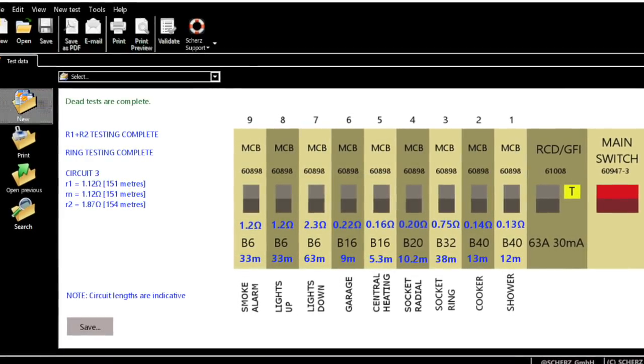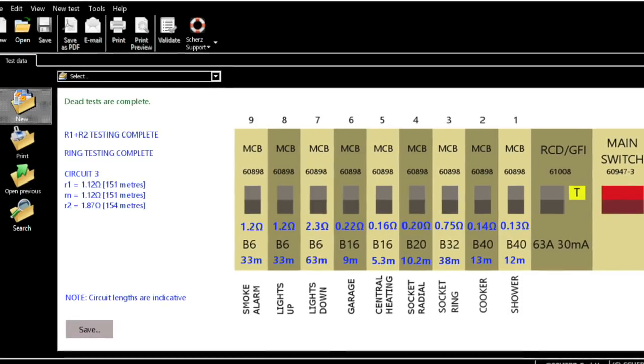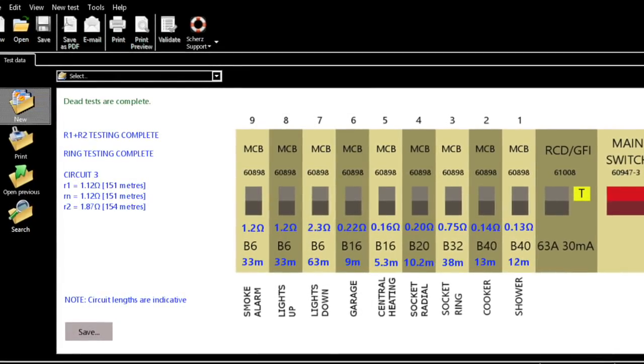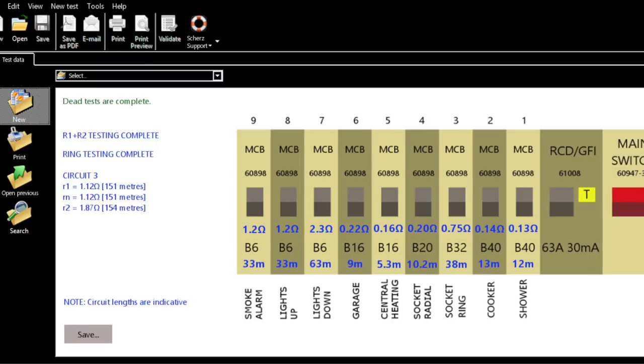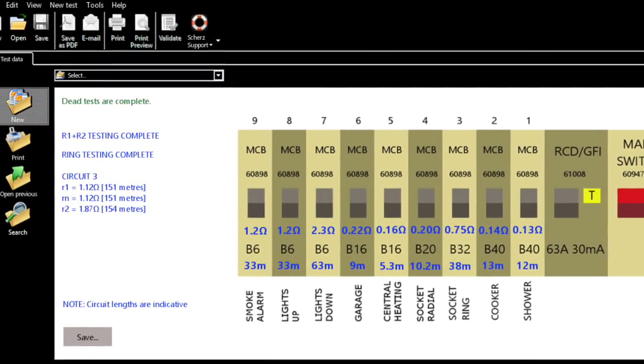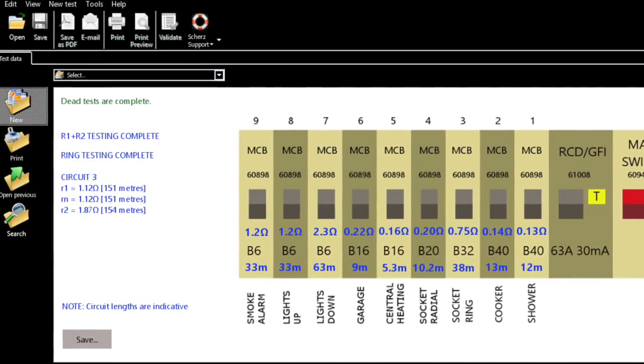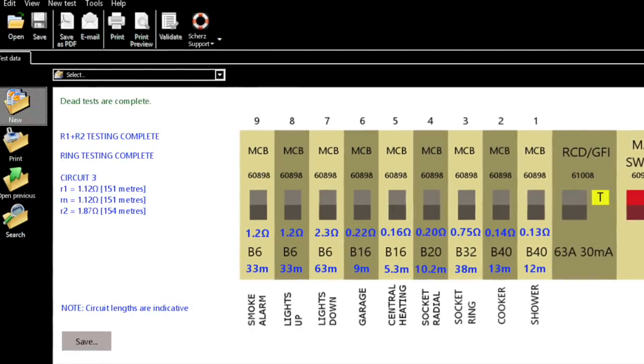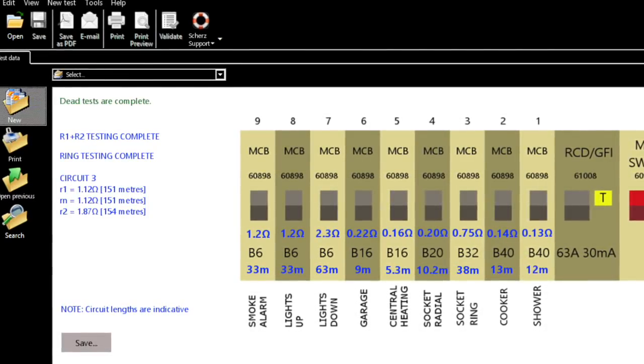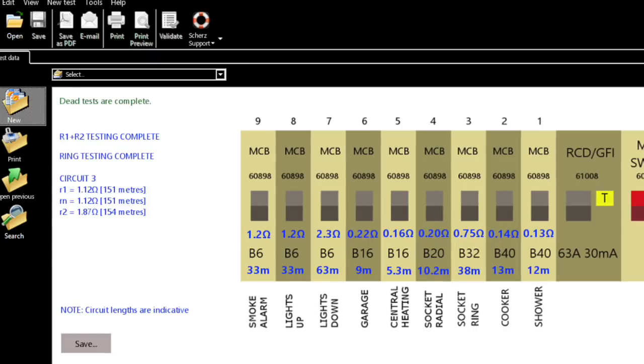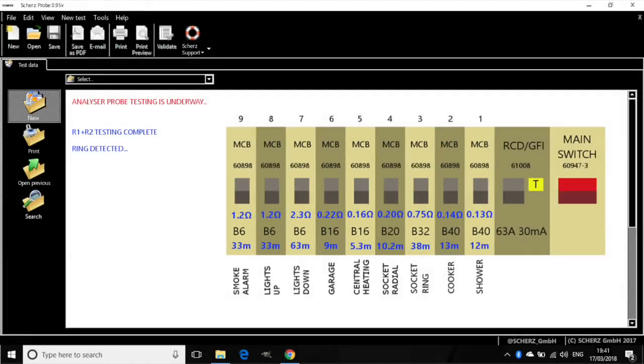So the ping pulse on fuseway 1 is at a different frequency from the pulse on fuseway 2 and so on, with up to 25 fuseways being supported. Although all circuits are tested simultaneously, the higher the impedance, the longer the result takes to be returned, it seems, but it's only fractions of a second and that one button click returns all your R1 plus R2 results almost immediately.